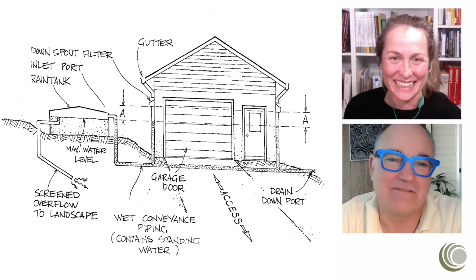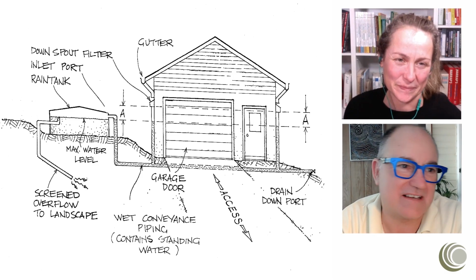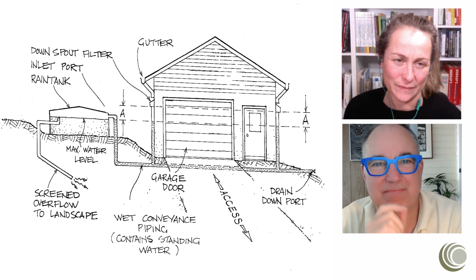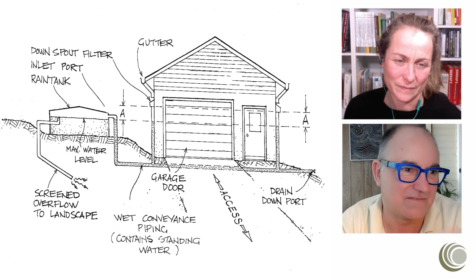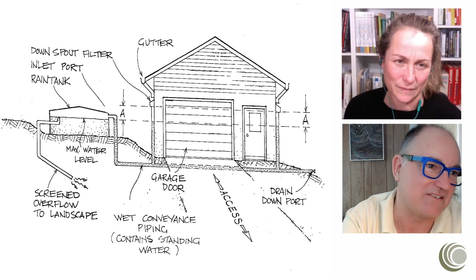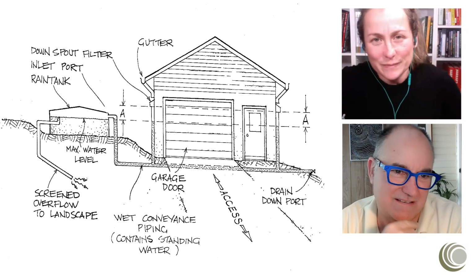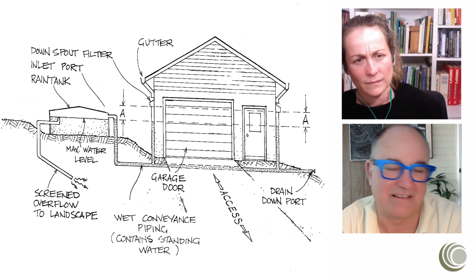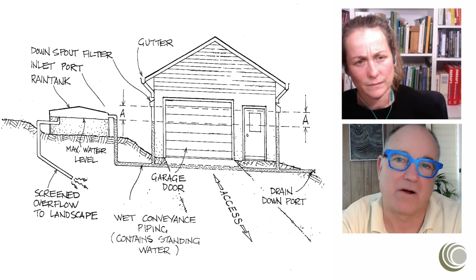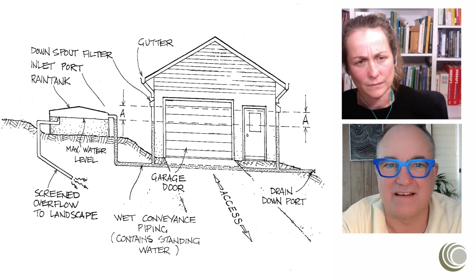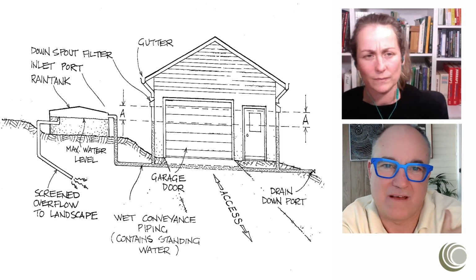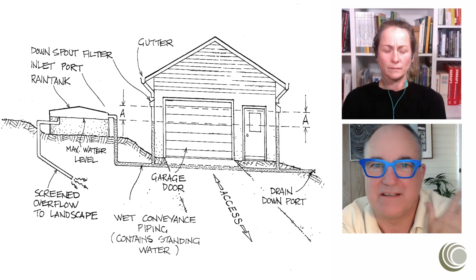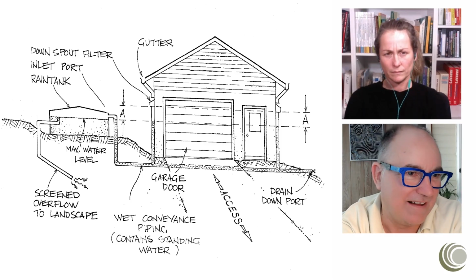Okay. So what we know is there'll be entry and exit losses. A bit of hydraulics. Apologies for that. Water in a downpipe doesn't flow as a jet. It flows, as we were talking about, and you showed that video just before, Michelle, as a spiral, and it's very rare for rainwater in that situation to flow as a jet. But that flow is broken at the downspout filter and the process starts again. So from the bottom of your downspout filter, rainwater will be completely driven by head, kinetic energy. Mm-hmm. So that point needs to be higher than the rainwater storage.